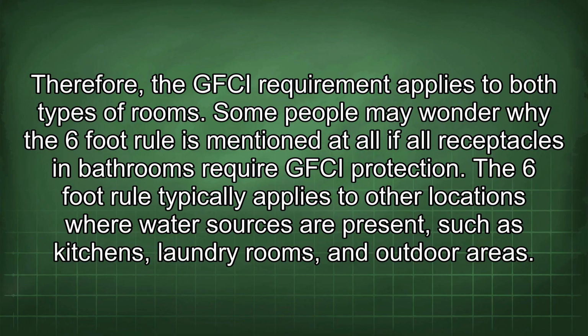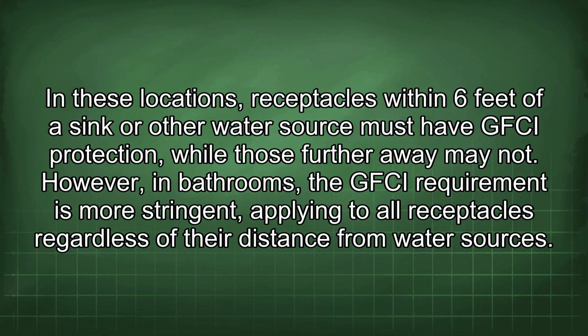Some people may wonder why the 6-foot rule is mentioned at all if all receptacles in bathrooms require GFCI protection. The 6-foot rule typically applies to other locations where water sources are present, such as kitchens, laundry rooms, and outdoor areas. In these locations, receptacles within 6 feet of a sink or other water source must have GFCI protection, while those further away may not. However, in bathrooms, the GFCI requirement is more stringent, applying to all receptacles regardless of their distance from water sources.